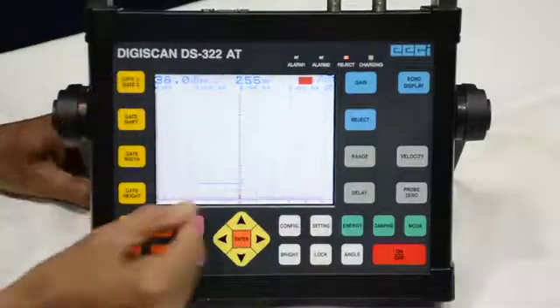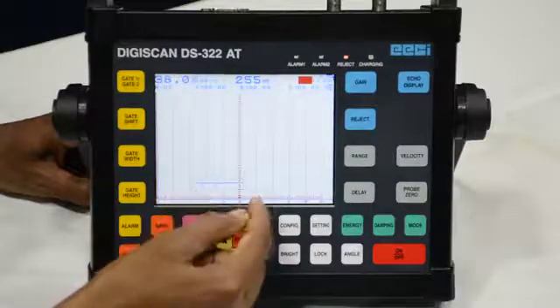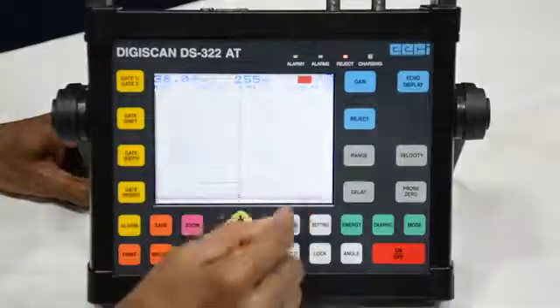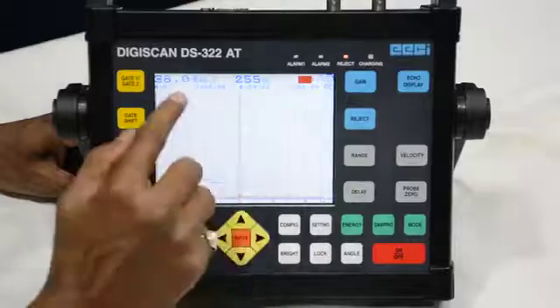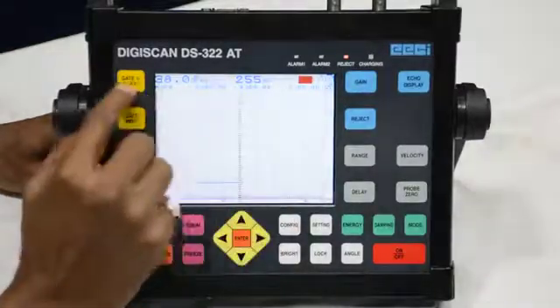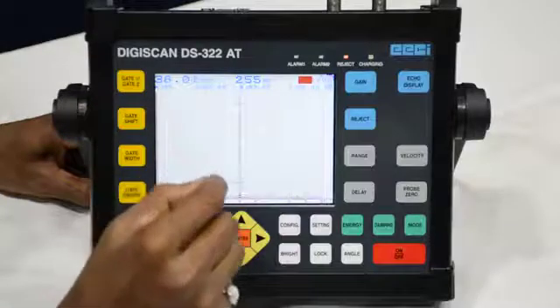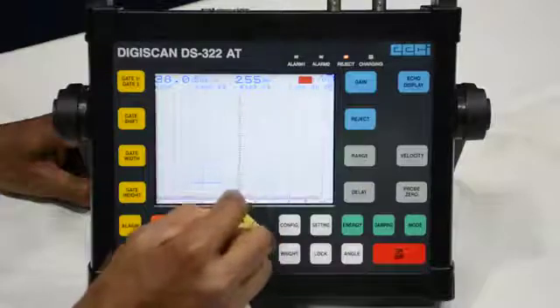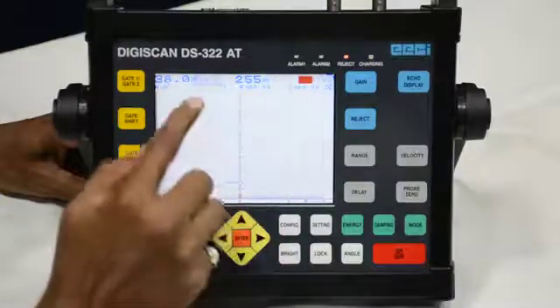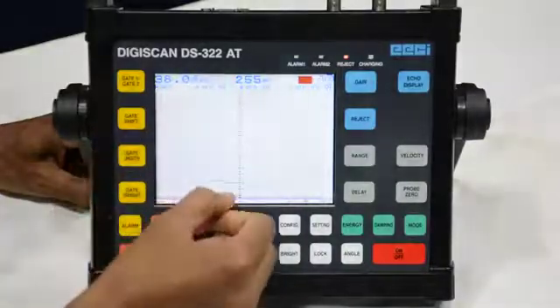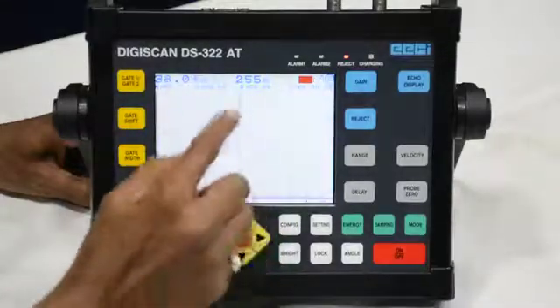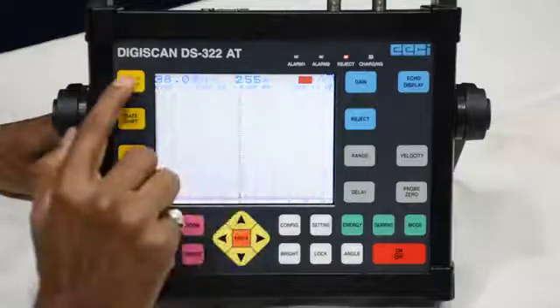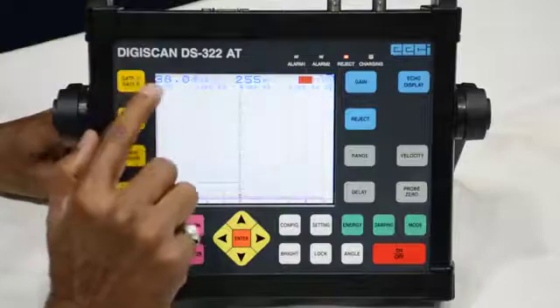This is the gate — it is shown here on the screen. If any echo is appearing on the screen and that echo touches the gate, all the values H, S, B, and D will be displayed. If the gate is not touching the echo, the data will not show. The basic function of the gate is to declare the location of the defect and the amplitude or severity of the defect. H is the intensity or amplitude of the echo, S is the surface distance, B is the beam path, and D is the depth. It will show all properties of that echo.